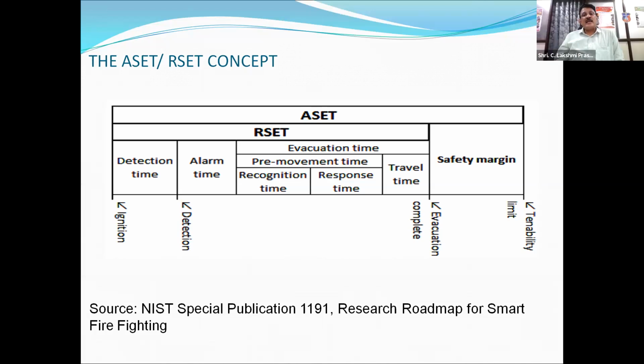The available safe exit time is the time up to which the tenable condition exists in a building. That is the longest time available, but the required time should be less than that. So you should not try to go until the available safe exit time in designing the staircases. People should be able to get out of the building within the available safe exit time, and the required safe exit time should be less than that. That is the design parameter that is taken in this performance-based design.